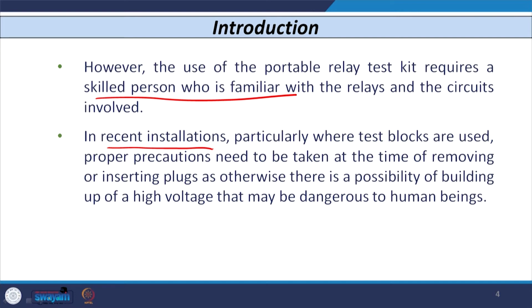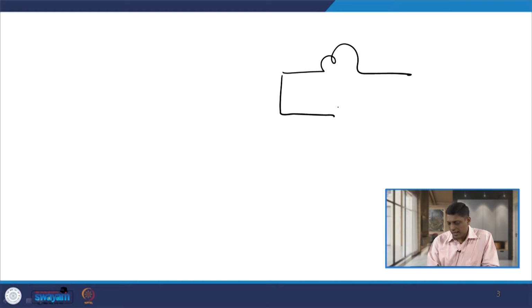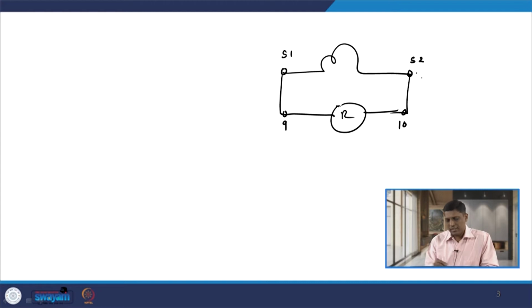In recent installations, particularly where test blocks are used, proper precautions need to be taken at the time of removing or inserting the plug. The best example is the current transformer. The relay is always connected across the secondary of the current transformer if it is an over current relay. This relay has a relay coil, let us say terminals 9 and 10, that is connected with the secondary of this CT, let us say S1 S2. When you want to carry out the testing of this relay, you have to remove it from the panel.